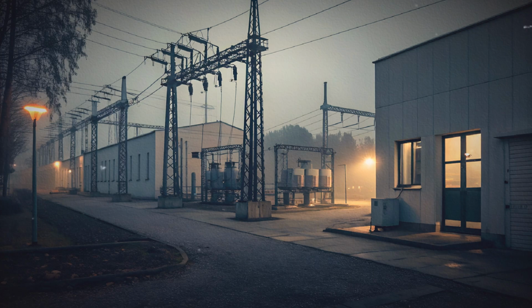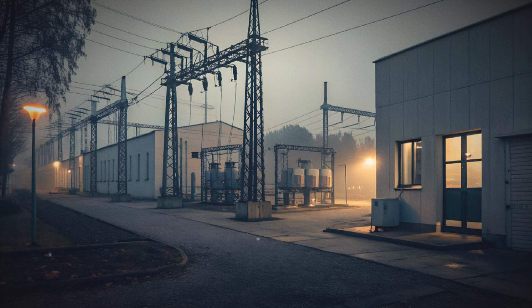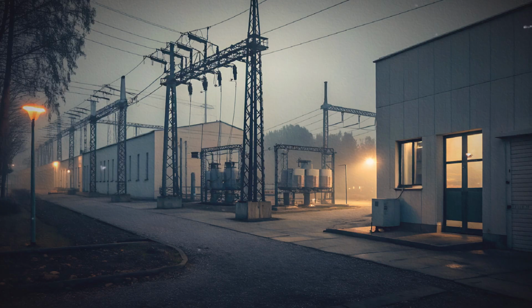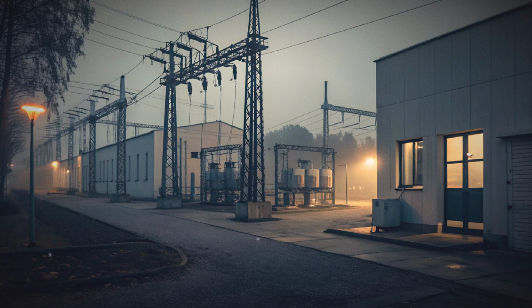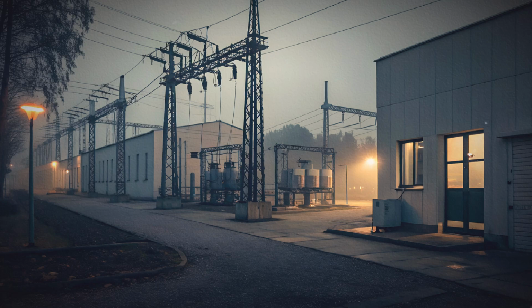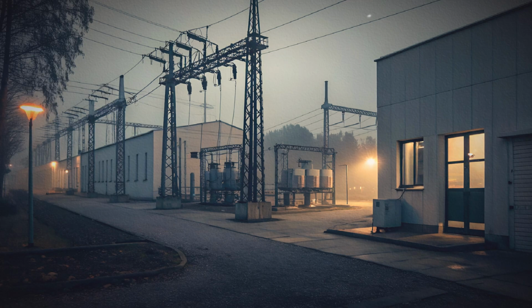Losses occur in transformers and switchgear. Core losses and copper losses reduce the net power available for delivery. Substations balance the efficiency of equipment with the need for flexibility, protection, and control. Placement of substation equipment, transformer sizing, and capacitor installation are planned to reduce losses across typical operating conditions. Planning also accounts for future load growth and the need to reconfigure connections as demand changes.